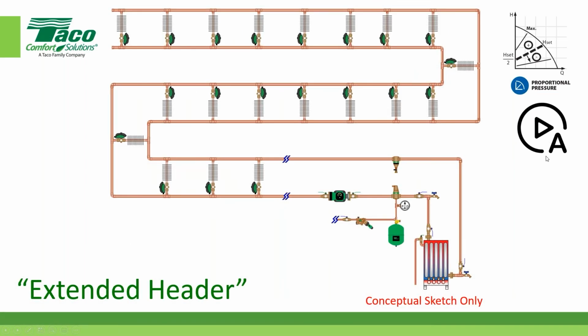Now, when is proportional pressure appropriate? Okay, now notice I've changed the name of this layout pattern. Generally you would understand what an extended header would be, because that little header that was in the mechanical room on that last example I gave you is not the same here. Let's say that these are the escutcheons and I'm leaving the mechanical room. I got a boiler, I got a supply pipe, a circulator, and I'm leaving. And I'm going out and I got a bunch of pipe out in the building, okay? I'm picking up all these different supplies and returns and everything, and it's all coming back, and I got a single return coming back. So I could stand in the mechanical room and look at this thing. If I know I only have one pump and I've got one supply and one return, yet it's a multi-zone system, you can make a pretty good assumption at midnight on New Year's Eve that this system is piped something similar to this, okay?